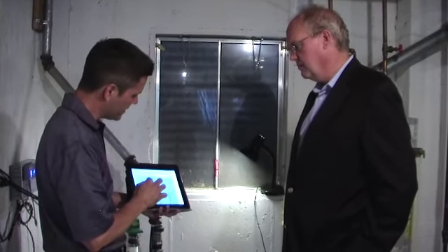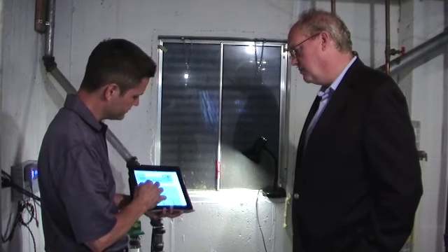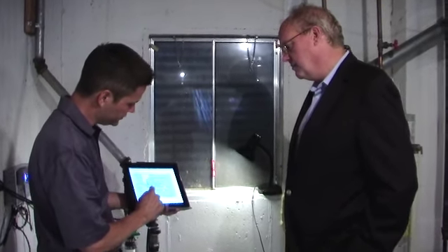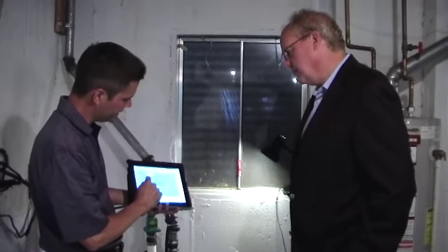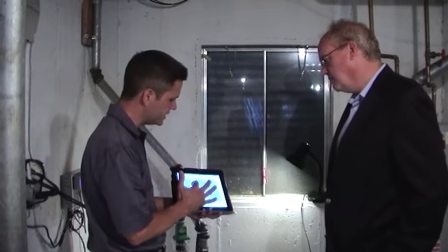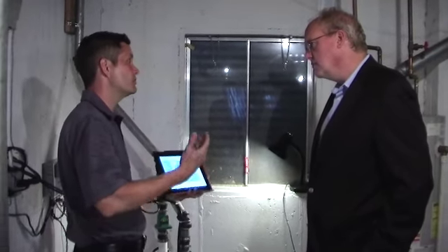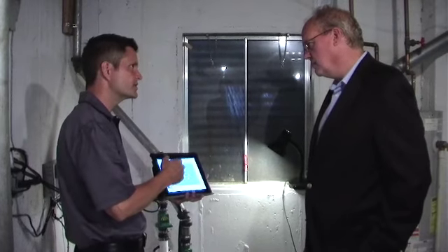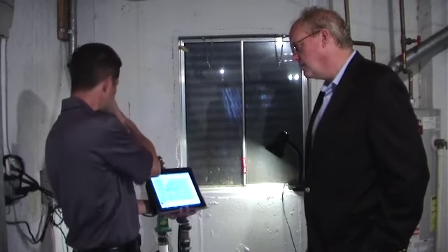Back on the config screen, I'm going to back up just for a second here. Back to this config screen, there's another field here called AOK Notify, and it's set for 120 minutes. That's just our testing default setting. You're probably going to want it for maybe 7 days or maybe even every day. What that'll do is, you're not getting an alarm every day, but you're kind of wondering maybe if everything's okay. The AOK just tells the unit, the controller here, go out, as long as there's no alarms and there's no other reason, go ahead and send an AOK email. Just a positive reinforcement that everything works.